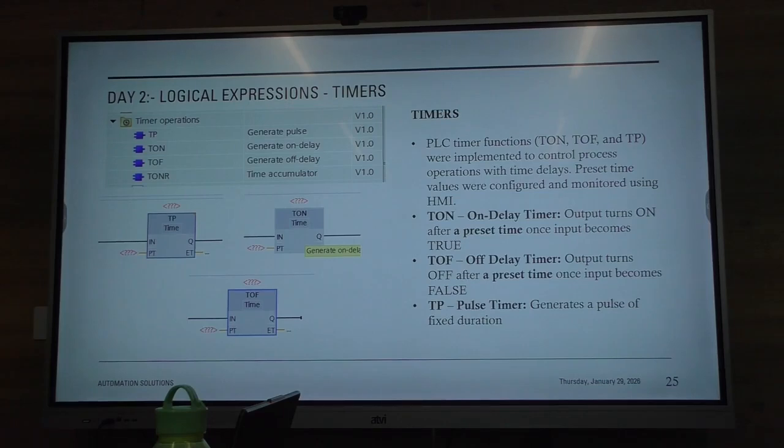Then at the input I give first 2 seconds, 4 seconds, then 7 seconds. So what will happen? For the first 2 seconds it will count the time. Then if you switch off the input, the timer will not go to zero. It will store the 2 seconds value. And again you give the input for 4 seconds. So it will be 4 plus 2, since 2 is already there, and it will now take 4 seconds, so it will remain at 6.